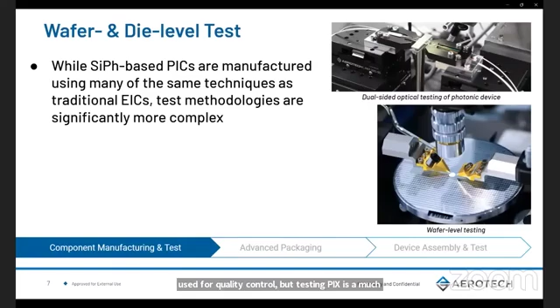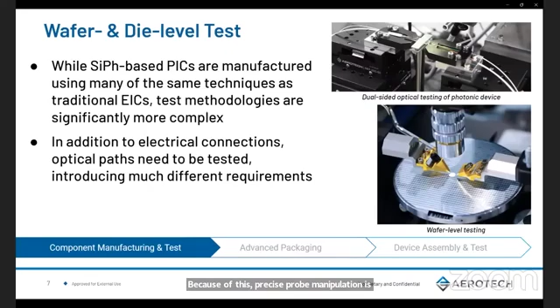This is because testing photonic integrated circuits requires testing of both the electrical and optical paths on the die. For electrical paths, a simple physical connection is usually all that is needed to conduct a test. But for optical paths, devices are typically sensitive to the positioning of the probes rather than just contact. Because of this, precise probe manipulation is required, including in several degrees of freedom and in complex kinematic arrangements.